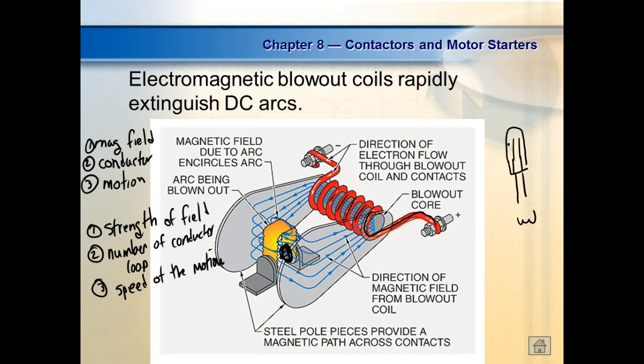What we do on AC is we put them inside troughs, right? You'll understand. Now on DC, big DC contacts, we'd have to blow them out this way. We had a big DC crane that one of the lifts, I don't forget what it was, kept running out and it kicked the overloads on it. And what was happening was we got up there on the crane and one of these big old relays, they were arcing across. What had happened is one of these paddles came loose and fell down. So we lost one side of the blowout, right? You understand? So it wasn't blowing that arc out.